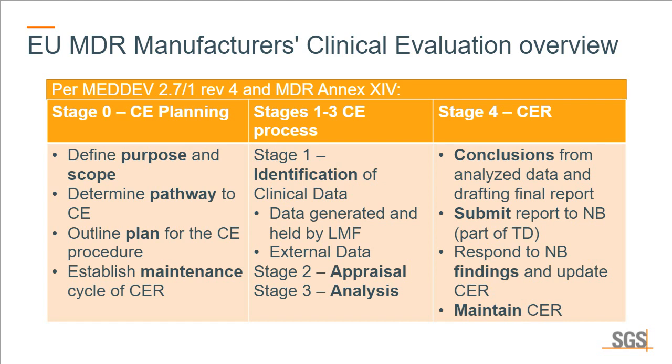Once you've done that, then you will need to have your conclusions from the analyzed data, and drafting the final report, you will submit the report to your notified body as part of the technical documentation. They will review that, then you will respond to the notified body findings and update the clinical evaluation report, and then you will maintain the clinical evaluation report in accordance with the plan that you have outlined in stage 0. So that's roughly the clinical evaluation process.